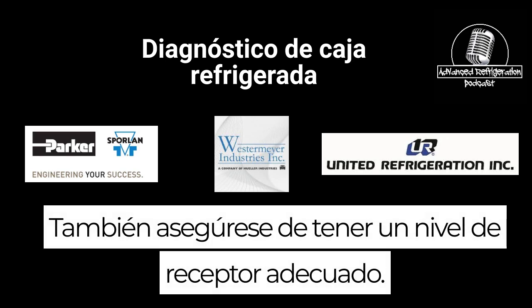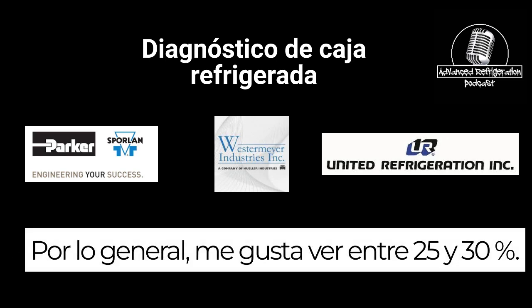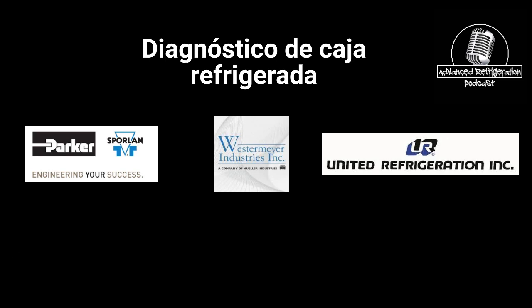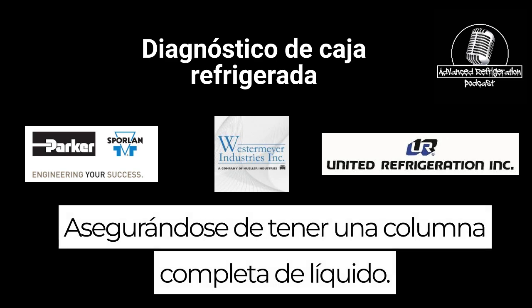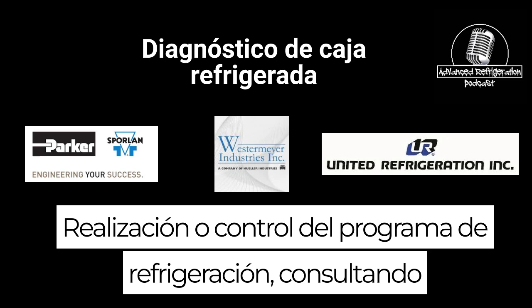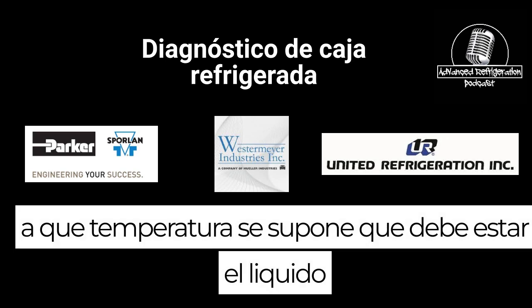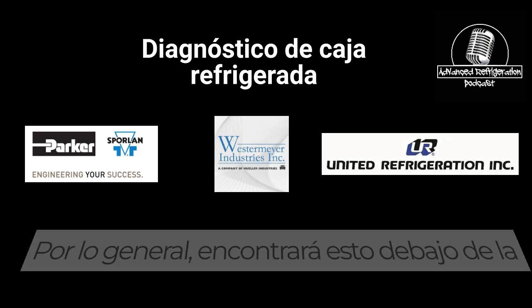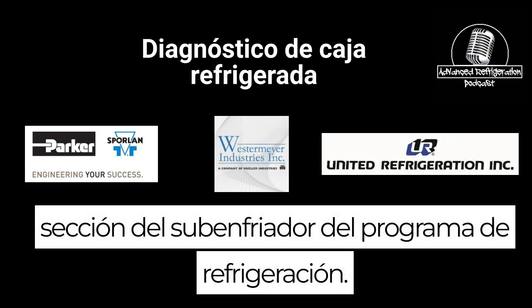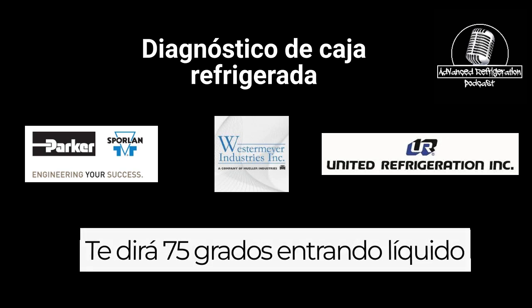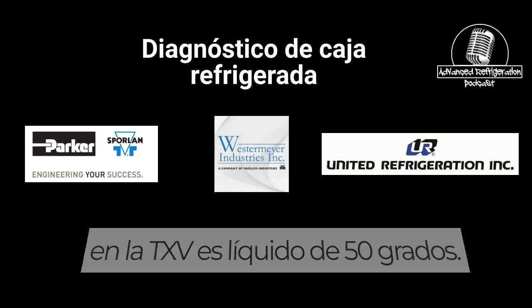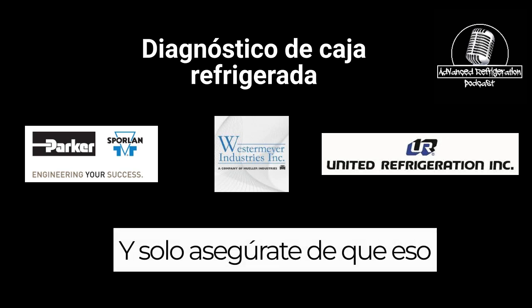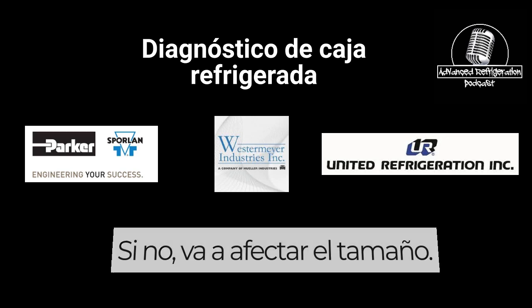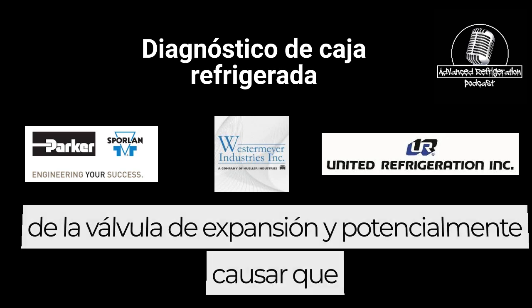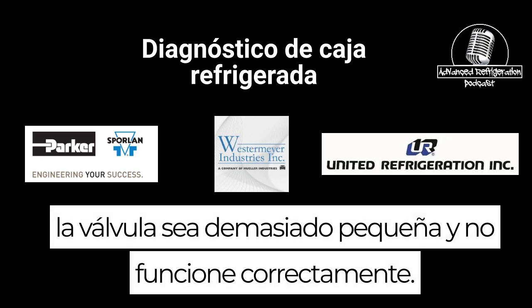Also, making sure you have a proper receiver level. Typically, I like to see anywhere from 25, 30%. Making sure you do have a full column of liquid, checking the refrigeration schedule, seeing what temperature the liquid is supposed to be entering into the TXVs. You'll usually find this under the subcooler section of the refrigeration schedule. It'll tell you 75-degree entering liquid at the TXVs, 50-degree liquid, and just make sure that liquid is at the proper temperature. If not, it's going to affect the sizing of the expansion valve and potentially cause that valve to be undersized and not work properly.